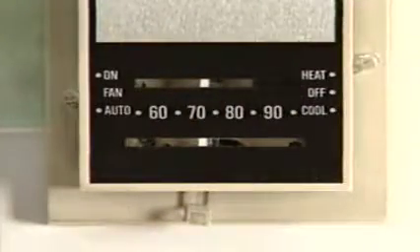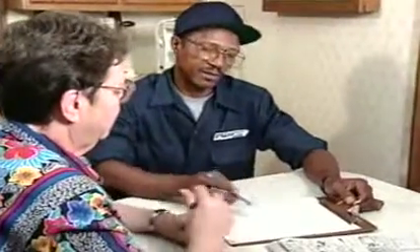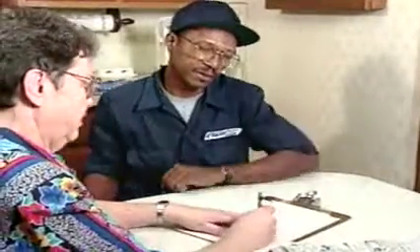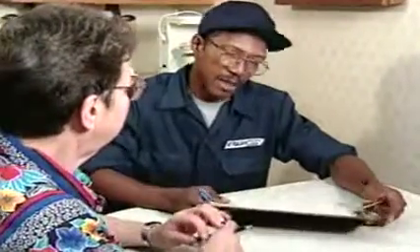Now that the unit is operating correctly, set the thermostat to the desired temperature. To wrap up the service call, explain the charges on the invoice, make sure paperwork is complete, and that you have answered any questions the customer might have. In that situation, a bad cad cell was the root cause of the problem. Now let's take a look at a service call where the complaint is the same—no heat—but the heating unit is different.